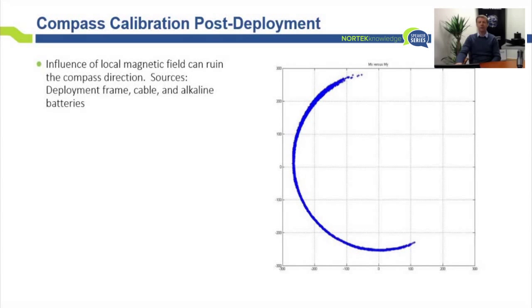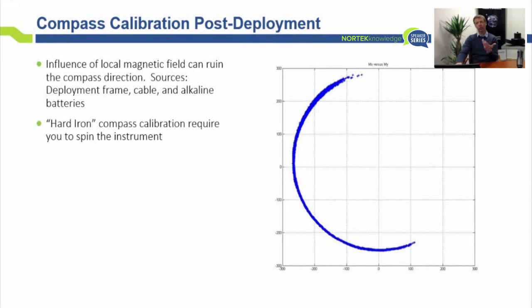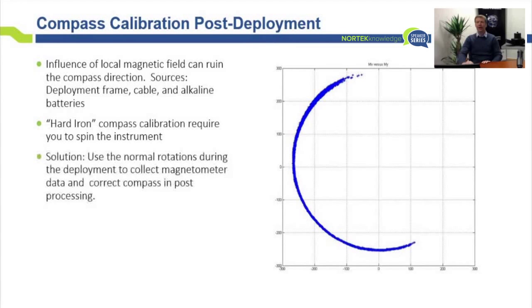So removing local magnetic fields, and the spinning portion of this operation that you normally do in the lab, you now simulate when you're deployed, assuming, of course, again, that the instrument is spinning. This particular plot is from an instrument that has been spinning about half a circle, moving back and forth around 180 degrees during the deployment. But this is enough. You don't have to go all the way 360. This is enough to check or correct the compass and get an improved directional estimate for your current data.